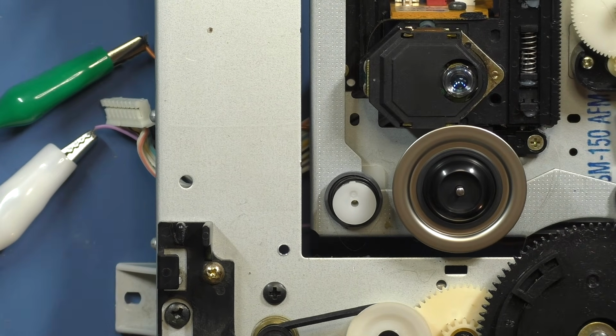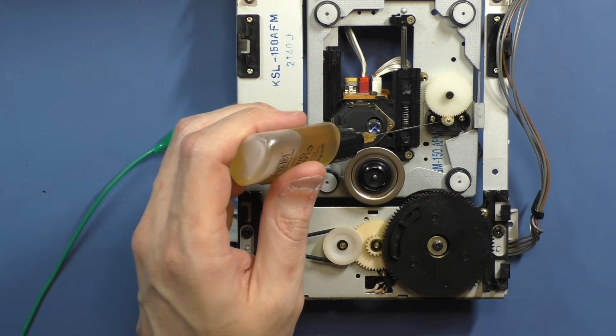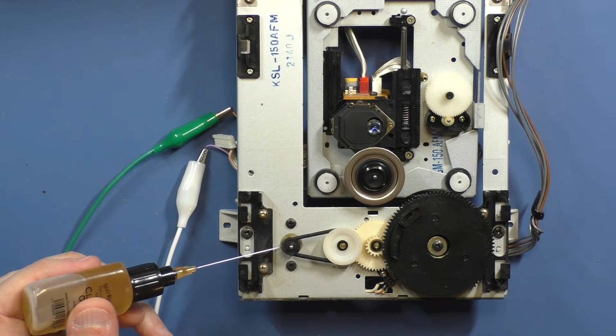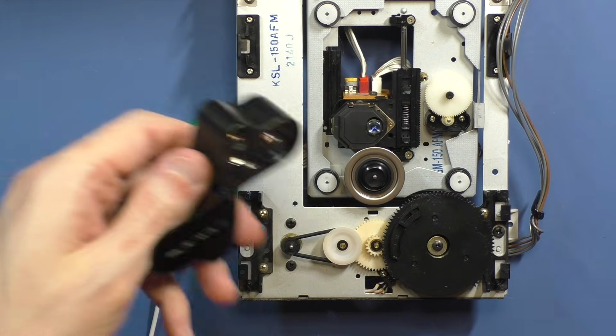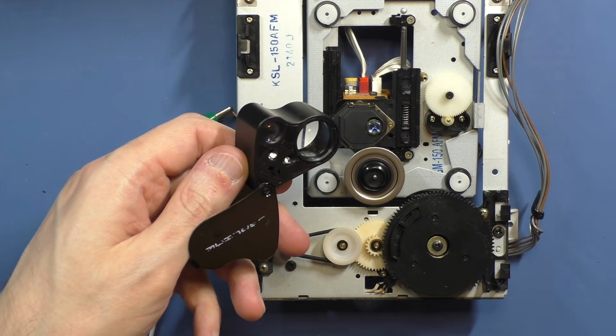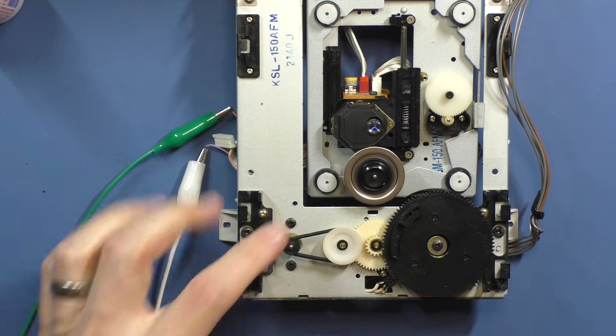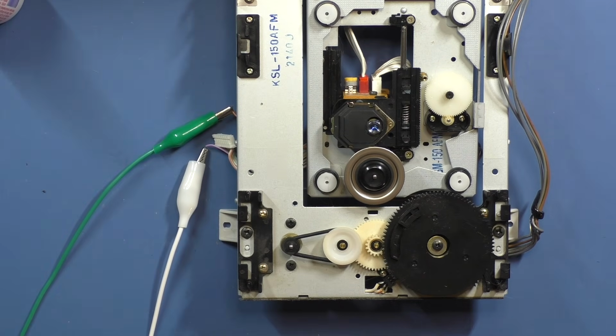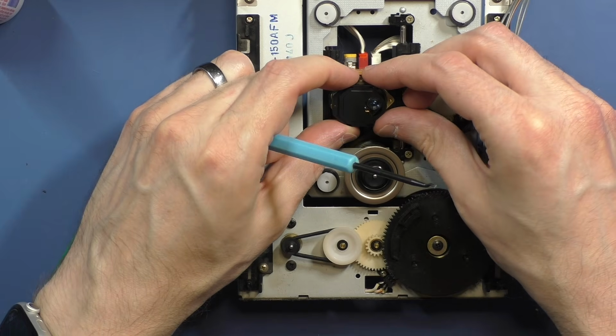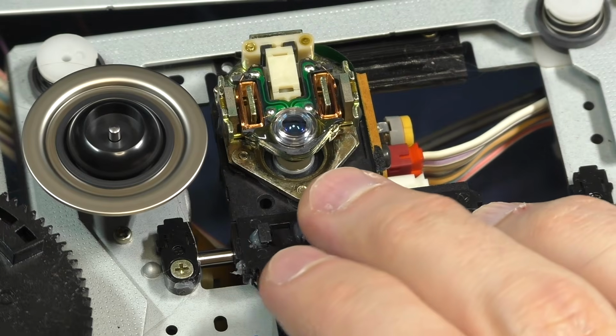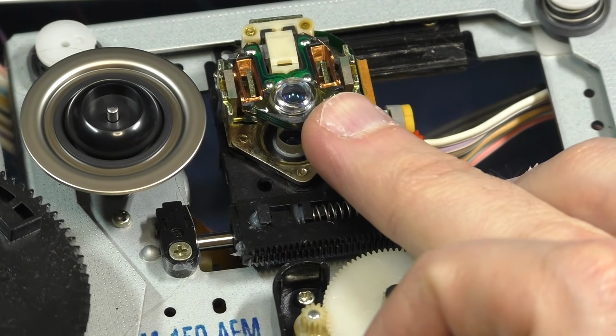Doesn't sound the quietest, so maybe that was the issue. Going to oil the other motors too. And lenses are often not as clean as they look. There's quite a bit of dust on that. In fact, since this is an original KSS 150, we can remove the shroud. That gives us access to the collimator lens underneath.